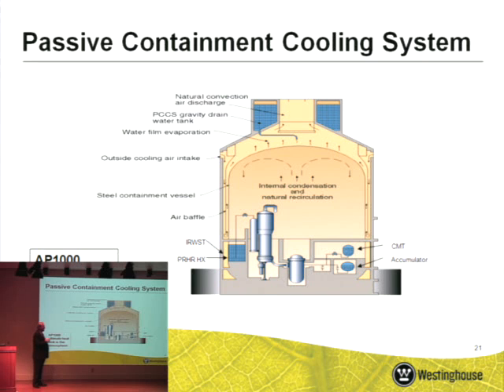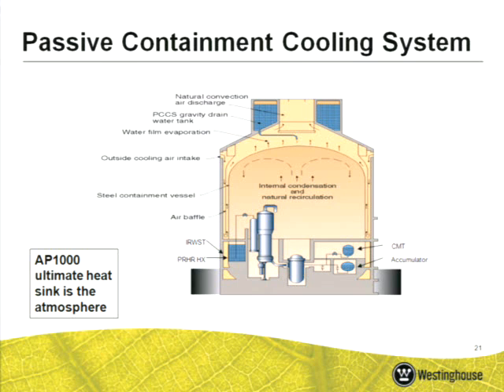The third barrier is containment. In this case, it's a steel pressure vessel, this right here. It's 1.75-inch steel designed for an internal pressure of 59 psi. And if the radioactivity barriers from the fuel and from the reactor coolant system were to be breached, then the containment holds the radioactivity so that it does not become a hazard to the public. And so in the case of AP1000, we not only use the function of the containment as a radioactivity barrier, we use it as a heat exchanger. We use this 1.75-inch containment shell as a heat exchanger.